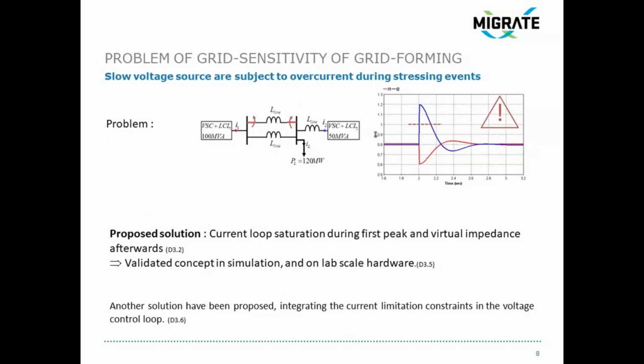inverters during events. Because when you behave as a voltage source, as soon as you have a small transient on the grid, like in this very simple case, you just trip one line without any fault. You have on the left a big inverter, on the right a small one, but a big load connected close to the small inverter. By just tripping a line, you have an overshoot of current that goes above the nominal. So it's very important to have a smart limitation of that. If you just go for a current limitation, you might end up with oscillations that would jeopardize the system.